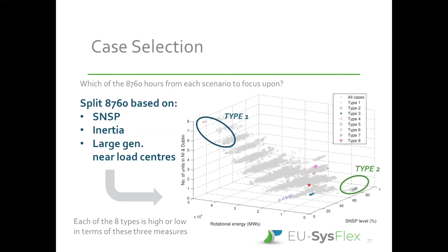Well, how does the rotor angle issue really come at us? It's a scarcity of synchronizing torque or damping torque, which is pretty much talking about the loss of synchronism of units through that sort of non-oscillatory drift away as they slip a pole, or those big angular swings where the system pulls itself apart. This can be localized, so you can have one generator that just slips a pole on a fault or oscillates by itself, or it can be global, where you have larger groups oscillating or separating, which can drive that system separation. So we have a slightly different flavor of severity here, where the global problem in terms of rotor angle is a real threat to system integrity.